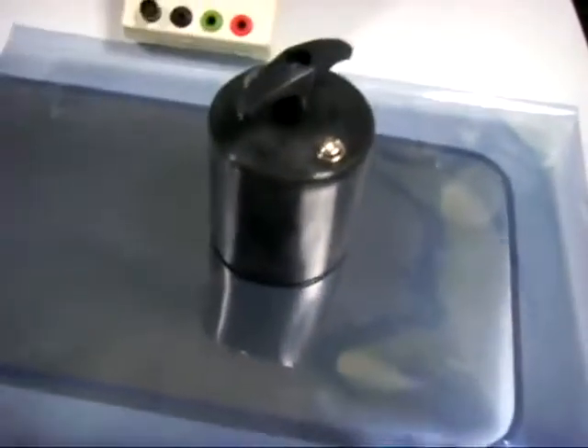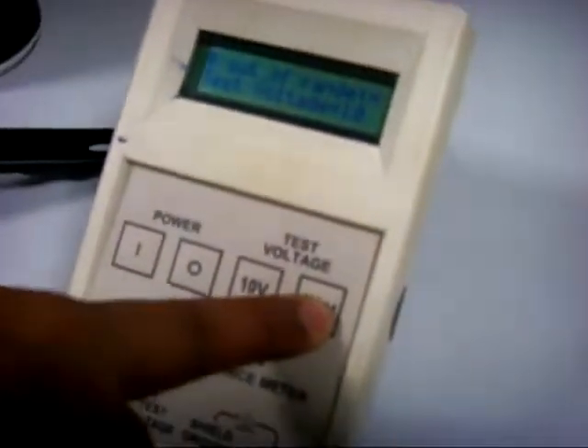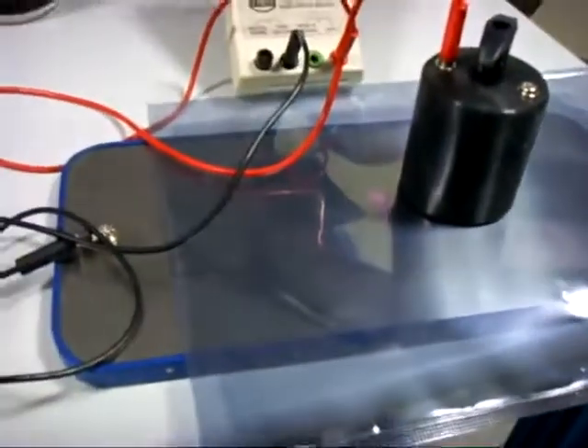We have to place this material on the stainless steel plate. One probe is picked up on the material. The foot plate, the SS plate, will be connected to the meter. We are selecting 100 volt. This is the volumetric resistance measurement. We are getting 3.6 into 10 power 9 ohms.